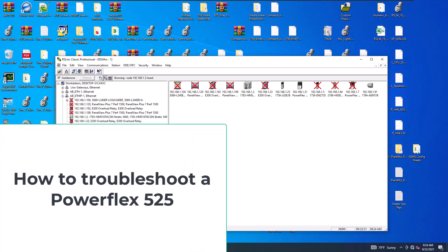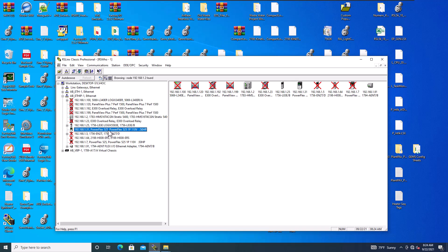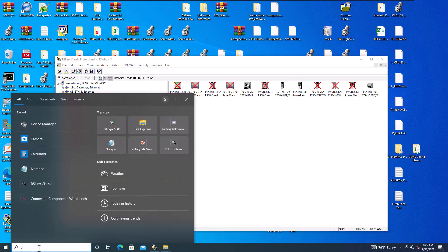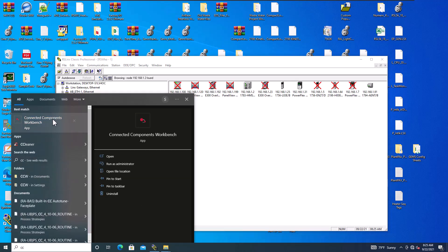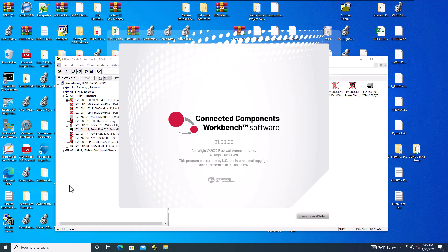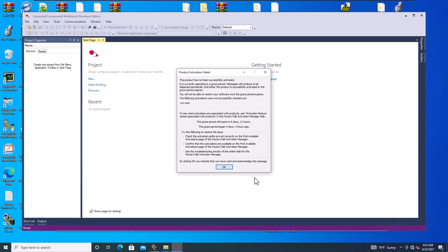This video will be how to troubleshoot a PowerFlex 525 drive - some common things you can look at and easy ways to go about it. This can still be used through your actual ACD file. I don't currently have an ACD file with that PowerFlex drive installed in it, so what I'm going to do is open up CCW, which is Connected Components Workbench. I can upload the drive to see its actual current state and what its history is.